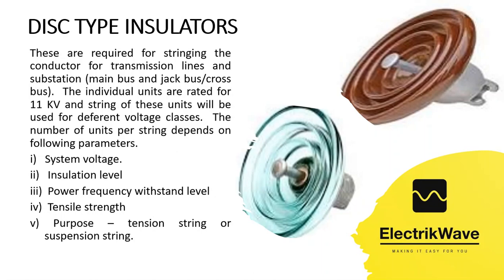The number of units per string depends on the following parameters: 1. System voltage, 2. Insulation level, 3. Power frequency withstand level, 4. Tensile strength, 5. Purpose — tension string or suspension string.